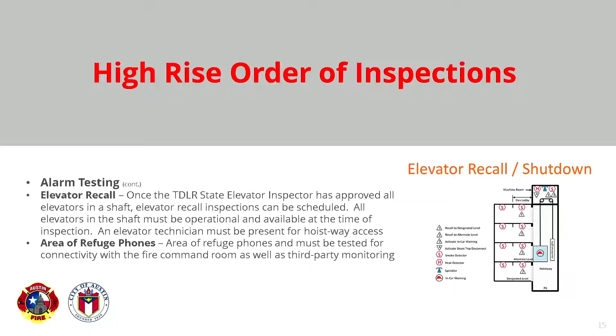Area of refuge phones are something that doesn't have to be tested prior to the uploading of the SIA report. So normally we'll put that off closer to the end, because we've got that 21-day to 30-day buffer of time that we're waiting to get the SIA report approved, during which we can work on area of refuge phones. And fire phones for buildings that were permitted prior to September 1st, 2021.